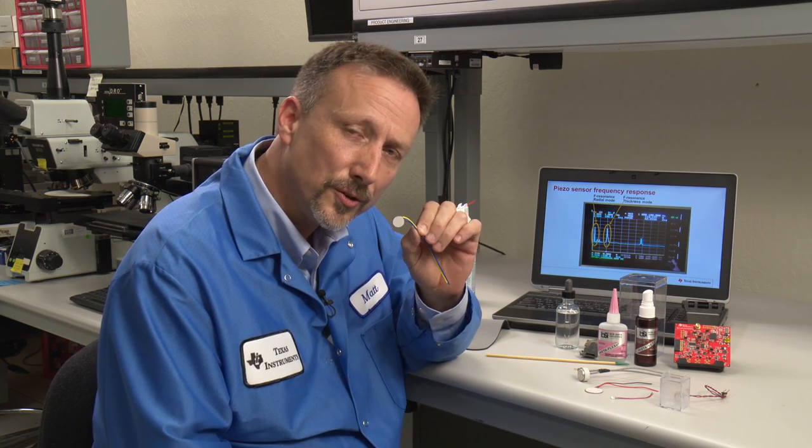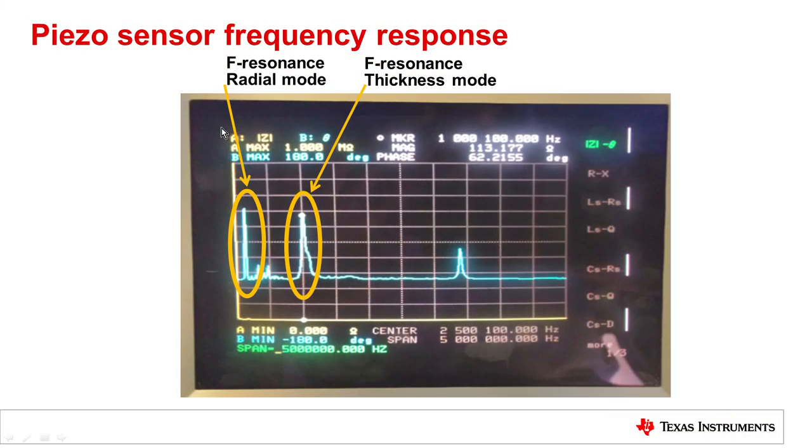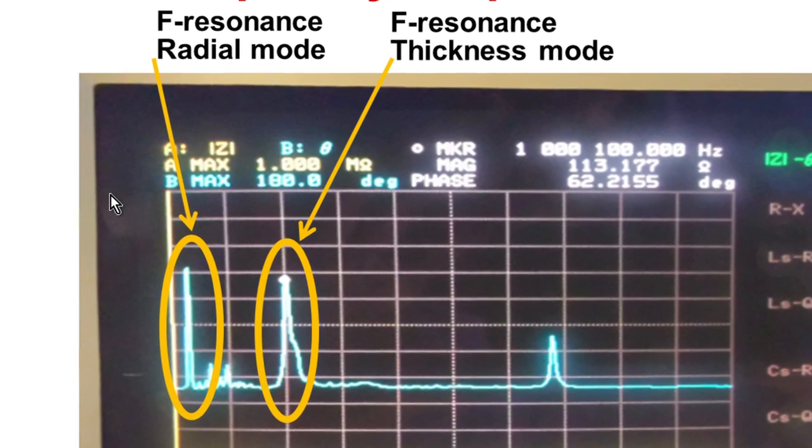For every transducer, there's two different types of resonances. In this slide here, for the frequency response of the transducer I just picked up, it actually has two key resonances. Every transducer that's shaped like a disc has two modes of resonance. A radial mode and an axial mode.